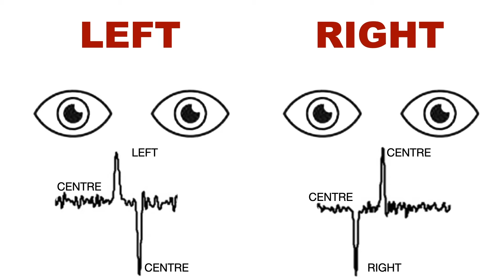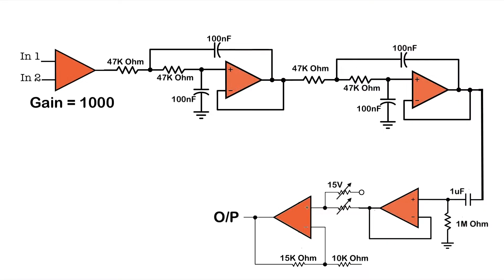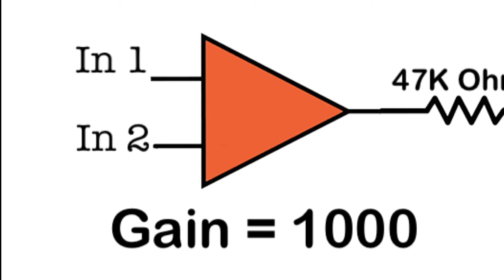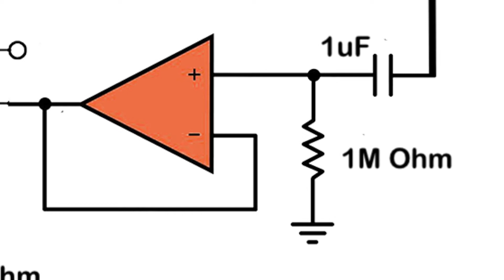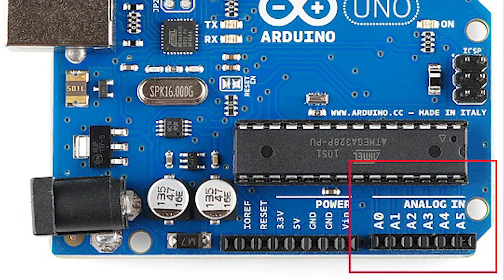The signal that we get from the electrodes needs to be first processed because it can be quite noisy and the amplitude is quite low. Hence, the signal needs to be cleaned first and amplified further. We use an amplifier to amplify our signal, then two low pass filters of 30 Hz and one high pass filter of 0.1 Hz. After this, we use a level shifter to shift the level of our signal. The signal is then digitized by the ADC on the Arduino and then fed to MATLAB, where it is analyzed in real time.